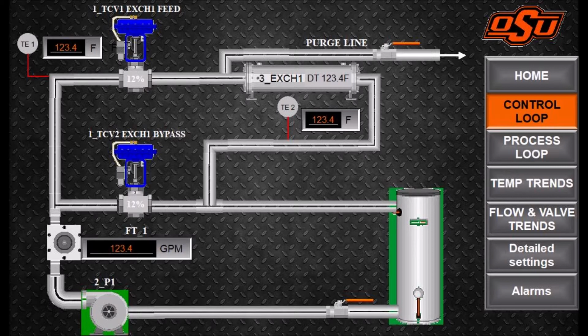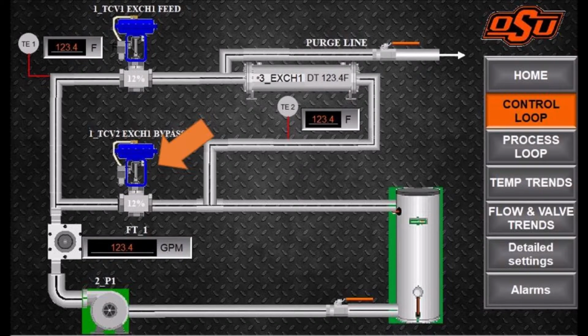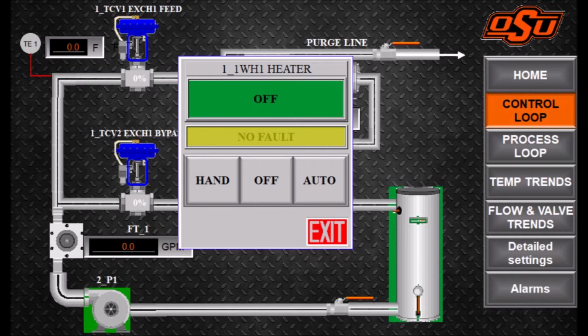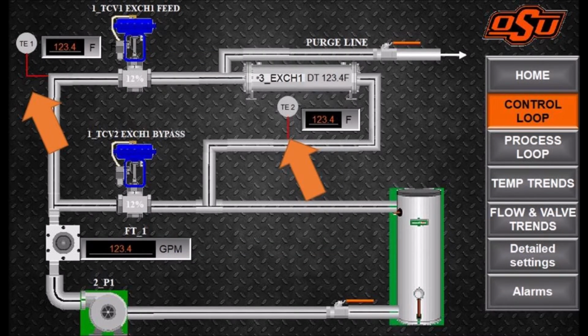We used W.E. Anderson sight flow indicators on both loops, which send a 0 to 10 volt signal to the PLC. The PLC is then scaled to show this value in gallons per minute. Each process valve is fitted with I to P transducers, which are actuated when sent a signal from the PLC. When in automatic mode, the PLC will open and close these valves based on set points in the program to heat or cool the process fluid. The operator has the ability to touch any field device on the screen to switch modes from auto to the manual or off position. Also shown are 2 temperature elements providing temperatures of the fluid out of the water heater as well as after it is passed through the heat exchanger.